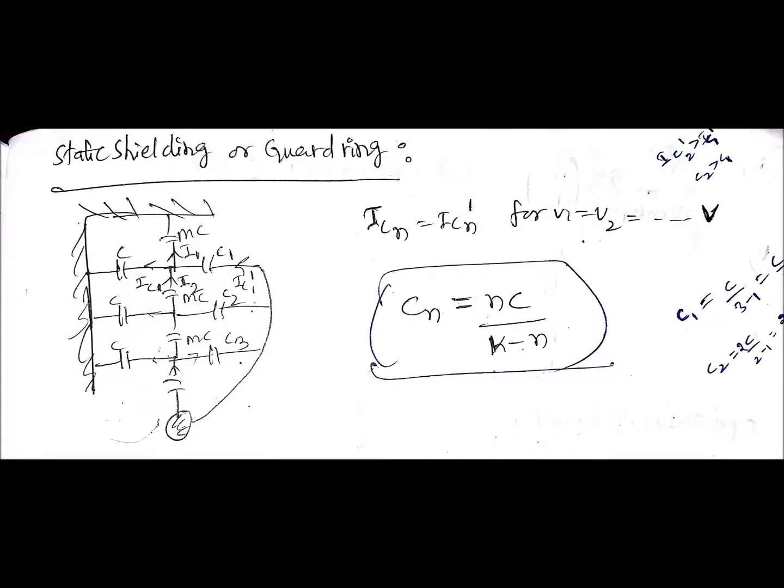One more method of making string efficiency 100% is static shielding or guard ring method. Here you are going to use one ring which is having the capacitances C1, C2, C3. Remember, C1, C2, C3 are not the capacitances of insulators. We have considered the capacitances of insulators as constant, like the actual case, and with that only you are making the voltages equal by adding the capacitances with a ring.